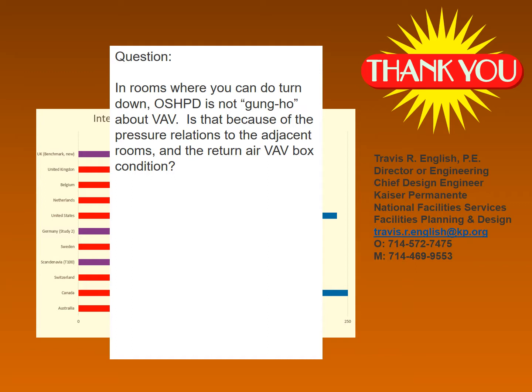Is it because of the balance of that room versus other rooms in the area, and putting in return boxes to control? OSHPD has some special rules unique to the California code. Rule number one is you have to have a return air VAV box for every supply VAV box, which makes VAV economically unfeasible, particularly in the existing portfolio. To do a VAV conversion of our admin wing, ostensibly by code, we'd need to add return air VAV boxes. That's a multi-million-dollar project, it's not going to happen. The second rule, related to that, is the corridor rule, where California code essentially says thou shalt not ever let a drop of air move to or from any corridor from any other space. Those two lines of code make VAV systems tough in California.